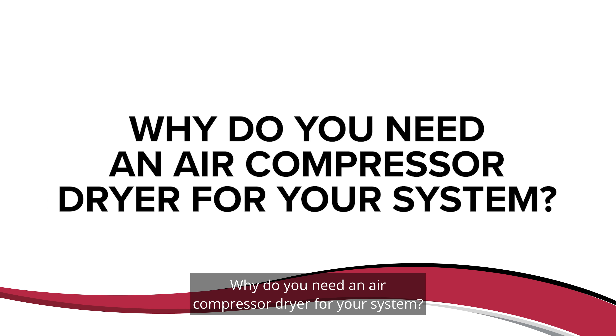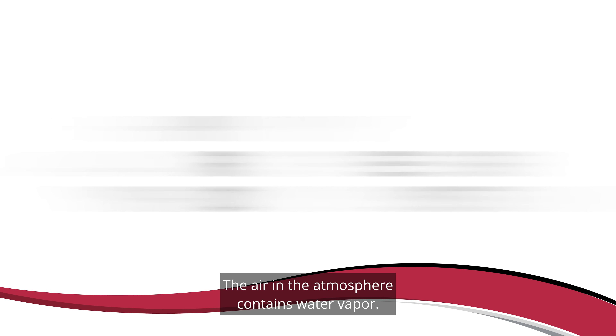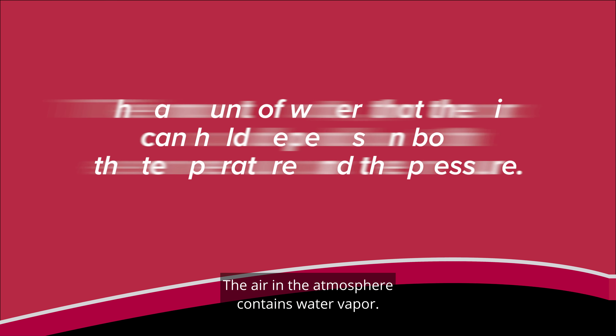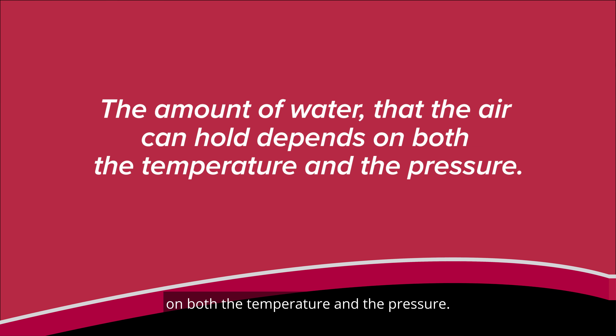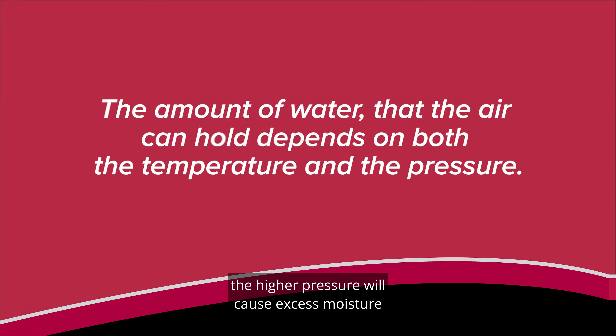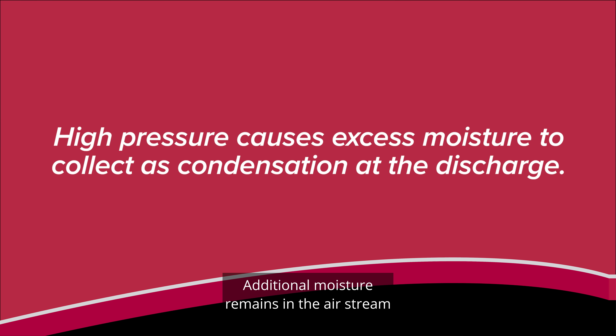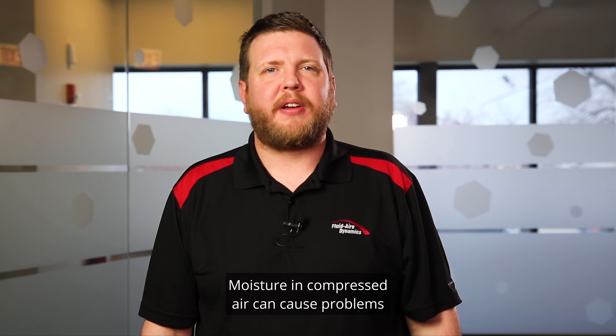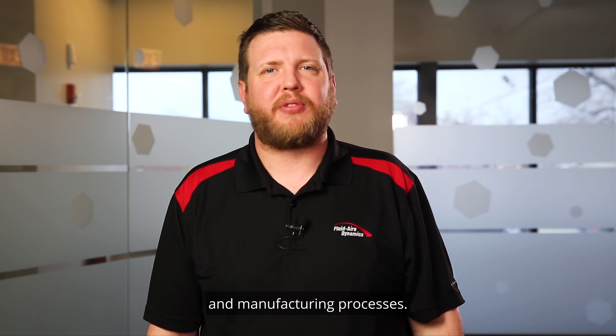Why do you need an air compressor dryer for your system? A compressed air dryer removes the moisture from the air that comes out of the compressor. The air in the atmosphere contains water vapor. The amount of water that the air can hold depends on both the temperature and the pressure. As air is compressed, the higher pressure will cause excess moisture to fall out of the air as liquid condensation at the discharge of the air compressor. Additional moisture remains in the air stream as water vapor. Moisture in compressed air can cause problems in the compressed air system, pneumatic equipment, and manufacturing processes.